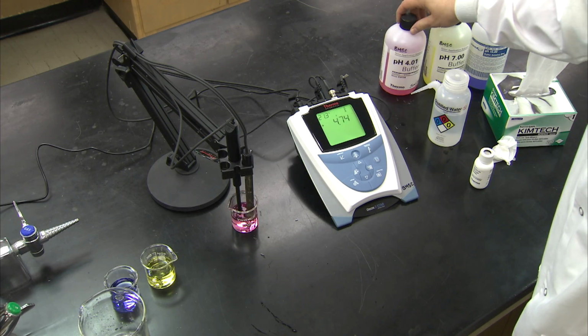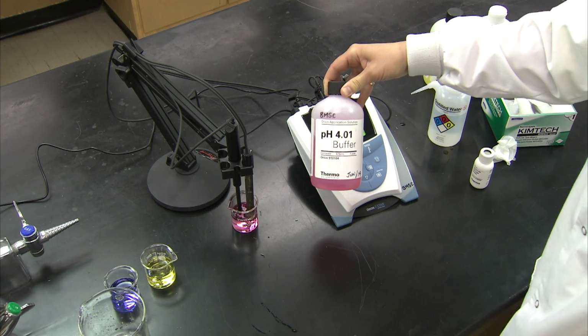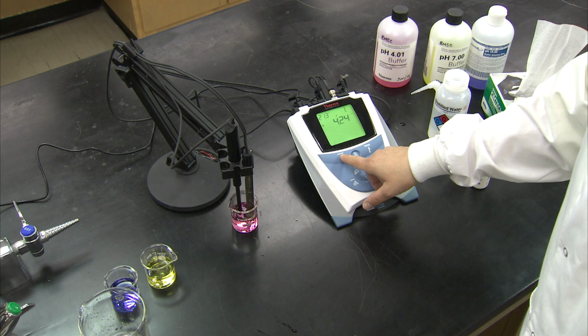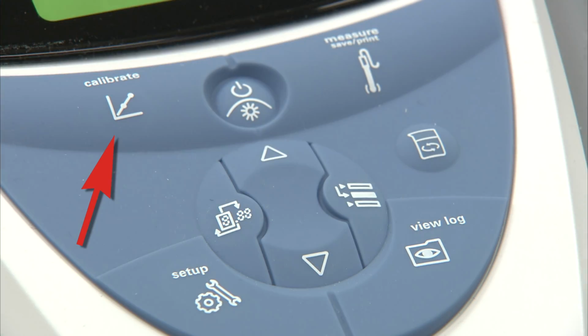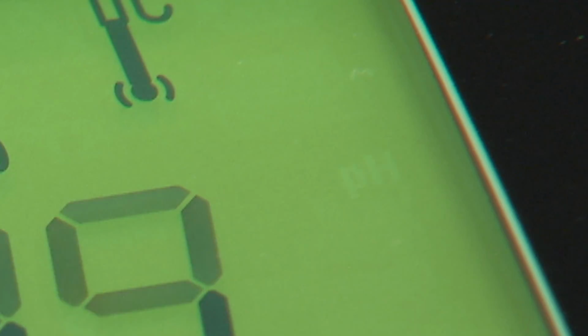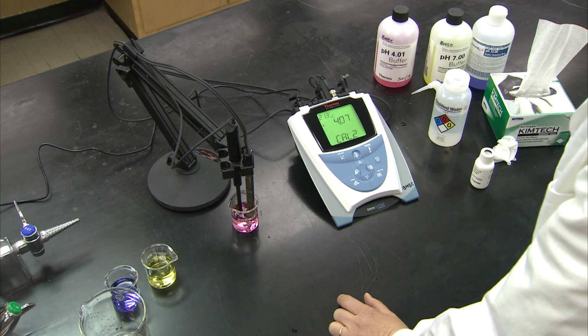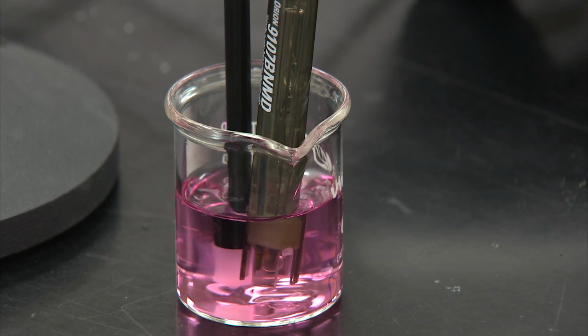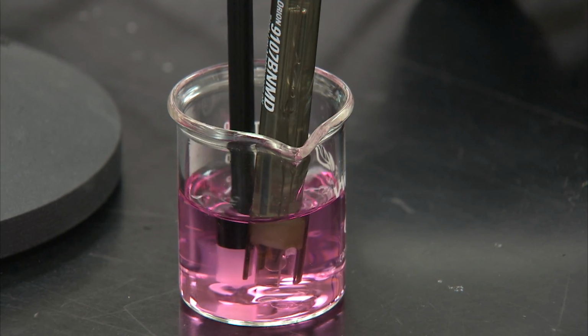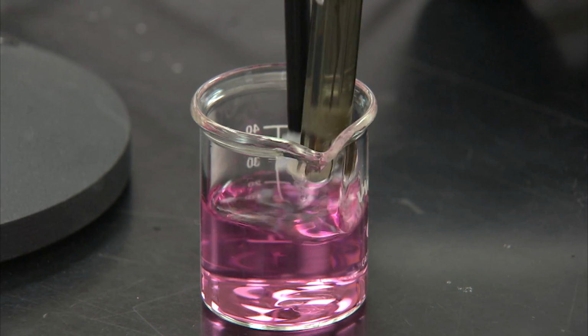The first standard is a pH 4 buffer. After immersing the probe in this buffer, the calibration button is pressed along with the stirrer button. When the pH icon stops flashing, you will press Calibrate again to move on to the next step. Before removing the probe, make sure the stirrer is shut off. Then remove the probe and rinse and blot as before.